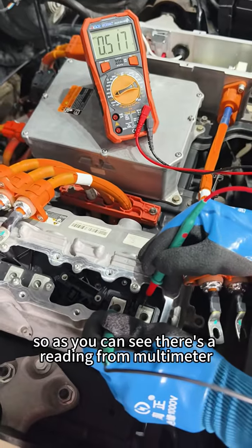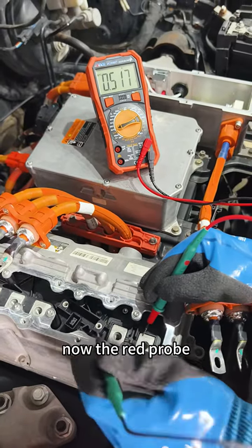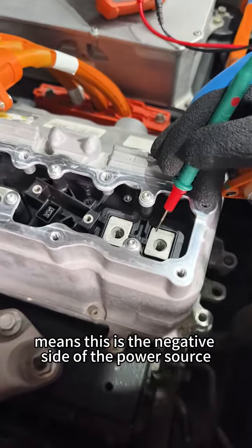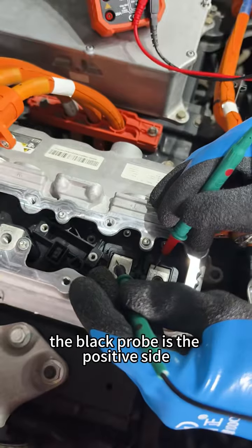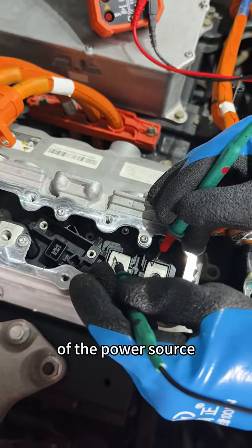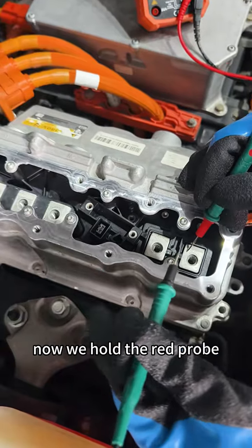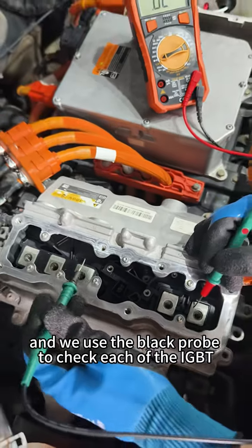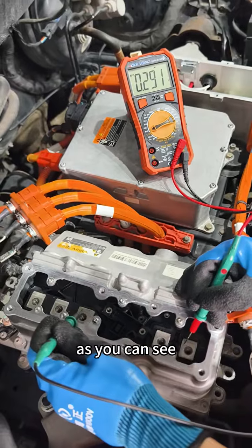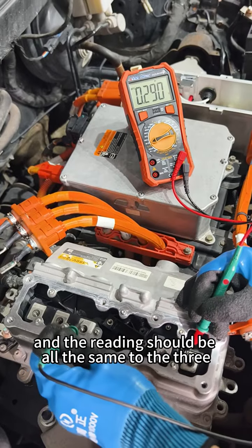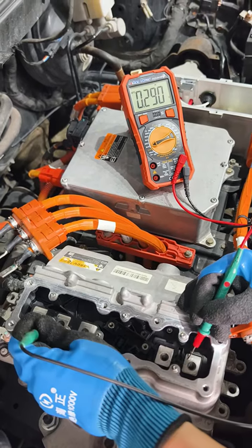So as you can see, there's a reading from the multimeter. Now the red probe means this is the negative side of the power source. The black probe is the positive side of the power source. Now we hold the red probe and then we use the black probe to check each of the IGBT. As you can see, there should be a reading and the reading should be the same for all 3.